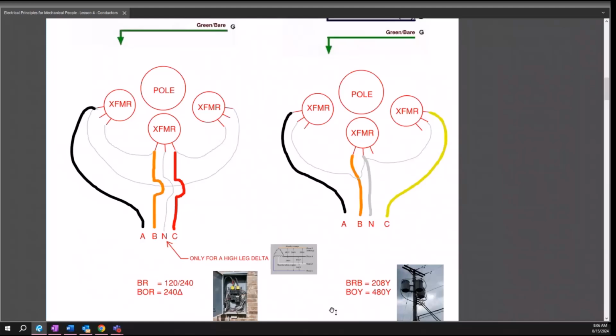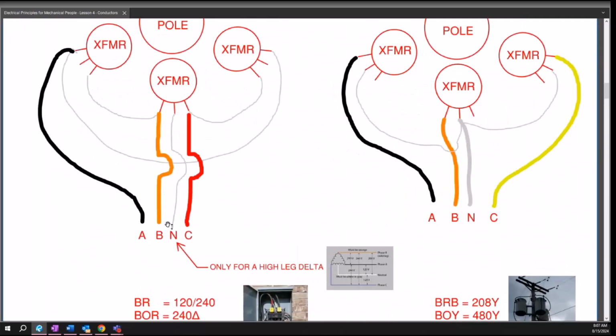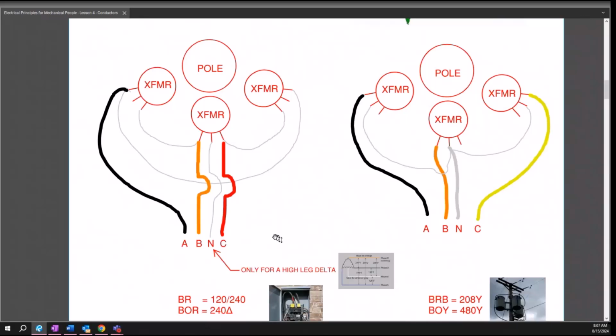The only change from that, this shall be this color, is on a delta. When you have a high leg delta, the B phase has to be orange. Like, period. There's no way around that. Okay. So whenever you have a high leg delta, you're going to have a neutral here. But if you just have a straight up delta configuration, there's not going to be a fourth wire. Okay. It's just going to be 3 wires with no neutral.